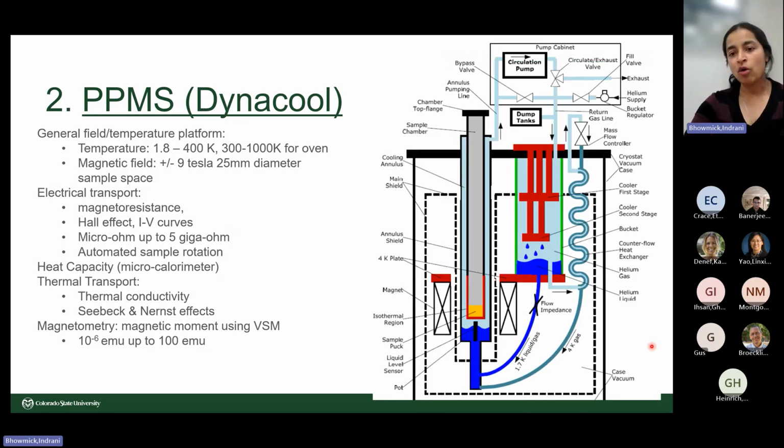So this is how the whole system looks inside, a schematic diagram. Let's not look into that. Our interest should be just this little isothermal region, because we want an isothermal region when we put our sample in. We need to know the exact temperature, because temperature is the basic energy we are putting in here. This is where our focus is. There are 2 magnets and our sample sits in this isothermal region, and there is a lot of helium flow and a bath to control the temperature.